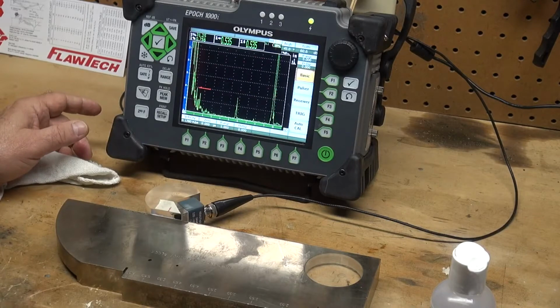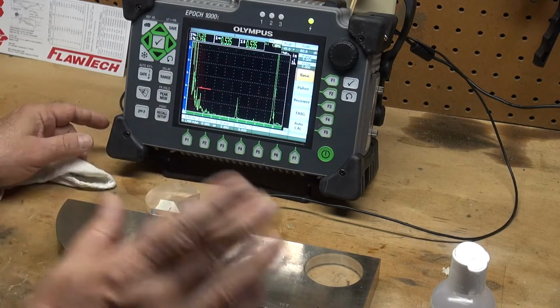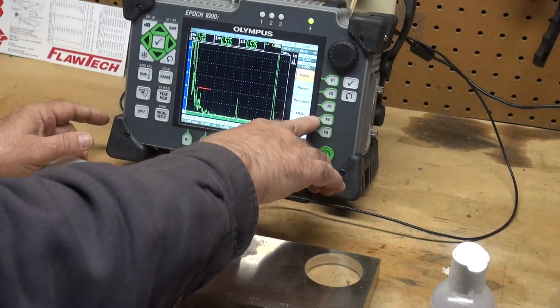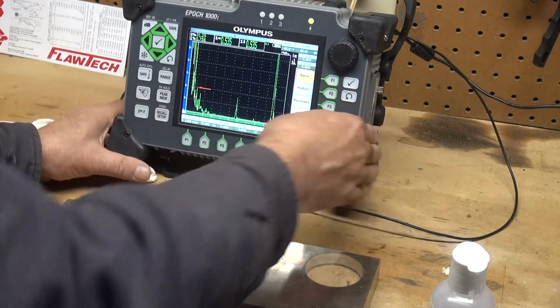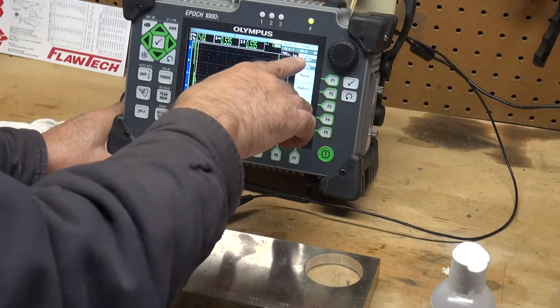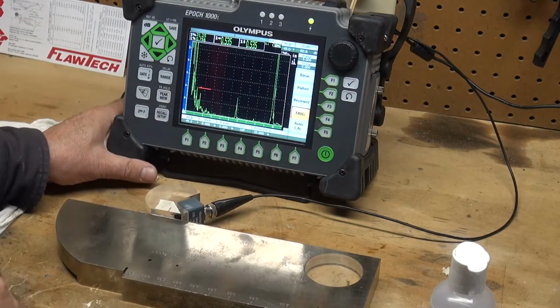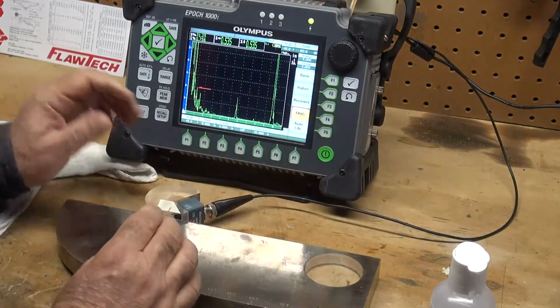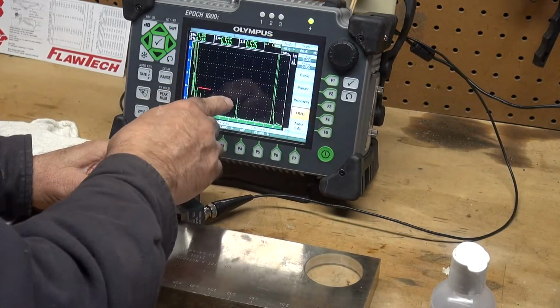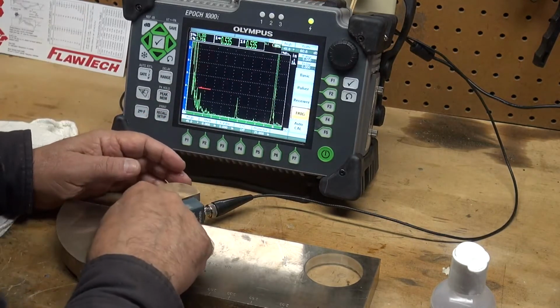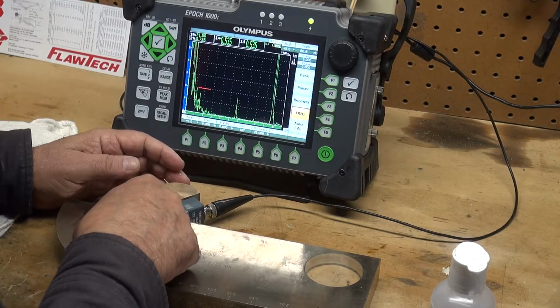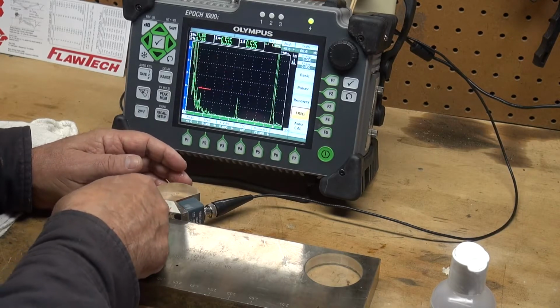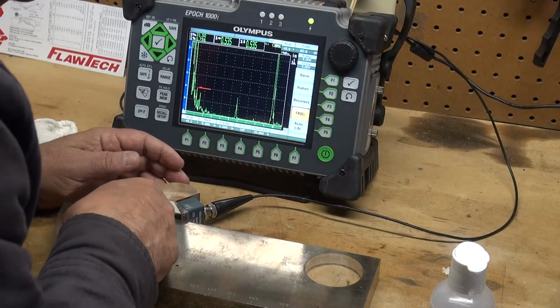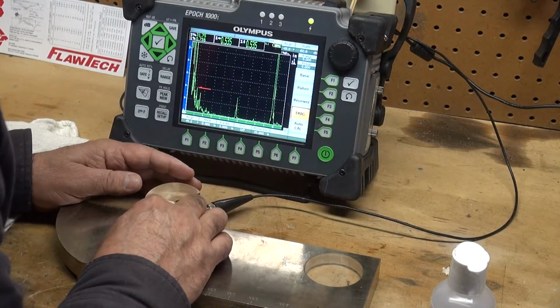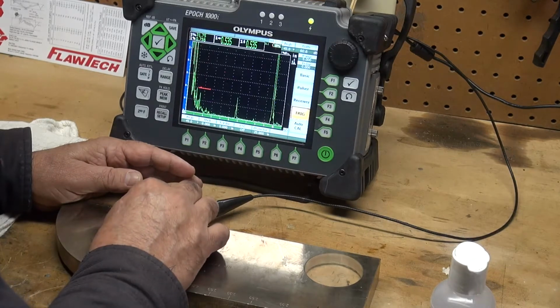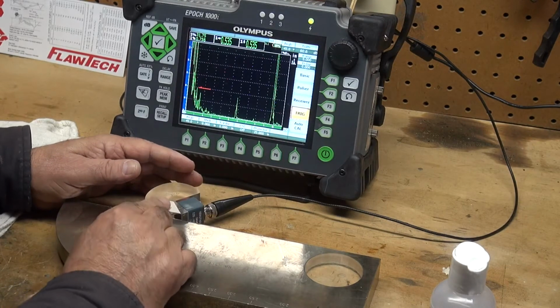And again, I'm using a 45 degree angle. And by the way, in our trig functions, I set my angle to 45 degrees because that's what the wedge that I'm using is. So I found the peak where that signal is the strongest, and I have a piece of tape here. I marked, that's my beam index point, that 0 machine mark on the IIW block. I marked on this masking tape where that point is. That's my beam index point.